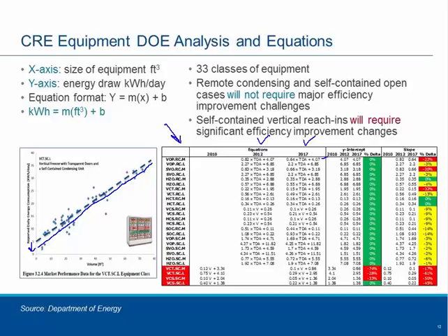The true test is really on these vertical guys that you see here. These vertical closed transparent and solid door, self-contained, low temp and medium temp, is where the drastic amount of energy reduction will be required. These are the pieces of equipment that end users need to be paying attention to for the future, and levels of improvement required to meet them can sometimes be drastic.